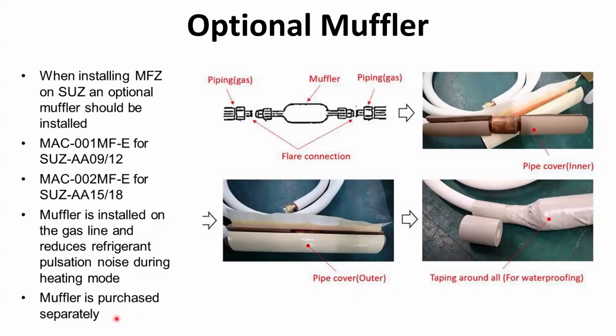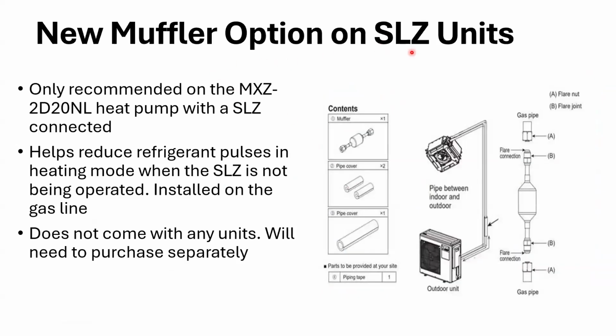Muffler is purchased separately. So everything here applies. You get all the pieces here. The only thing it does not come with is the tape. So again, this is being installed. I'll show you a picture coming up where it's installed. So muffler installation, and then you tape it, right? And we don't want any moisture getting in, mixing with our copper and condensation. So new muffler option on the SLZ unit. Only recommended on the MXZ 2D20NL heat pump with an SLZ connection for this.